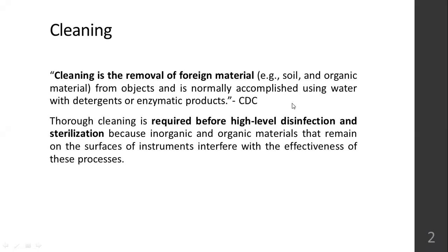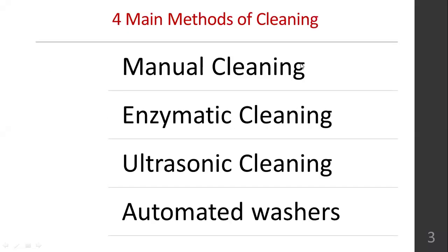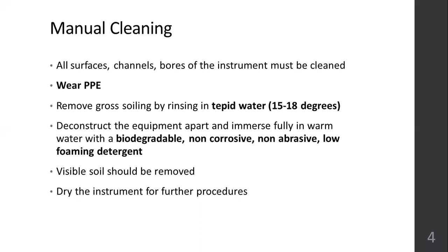So there are four types of cleaning: manual cleaning, enzymatic cleaning, ultrasonic cleaning, and automated washers. In manual cleaning, all the surfaces, channels, bores of the instrument must be cleaned. You have to wear PPE, personal protective equipment, while cleaning. And the main thing here is you want to remove all the gross soiling using tepid water, which is 15 to 18 degrees Celsius.